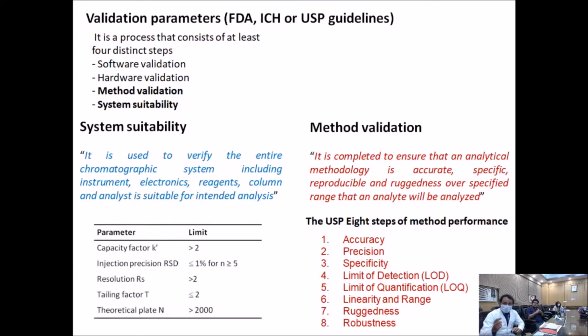The parameters I just mentioned: capacity factor should be more than 2, injection precision should be less than 1% RSD, resolution should be more than 2, and tailing factor less than or equal to 1.5 or 2. Theoretical plates should be more, so that efficiency will be more.